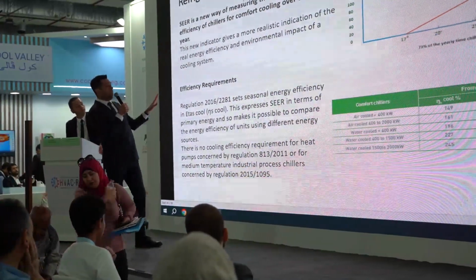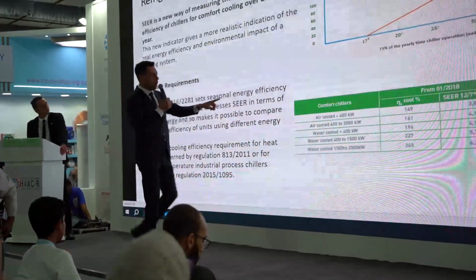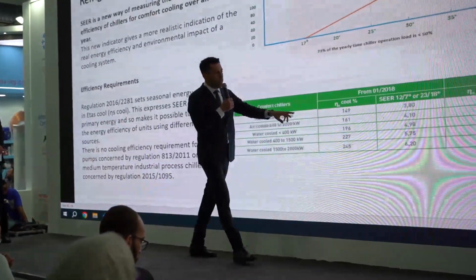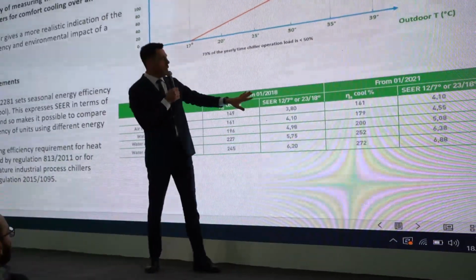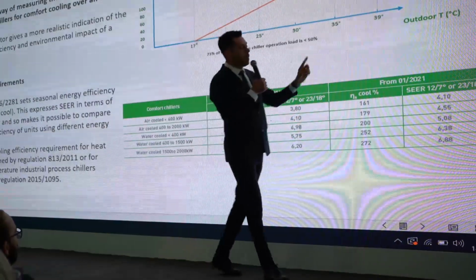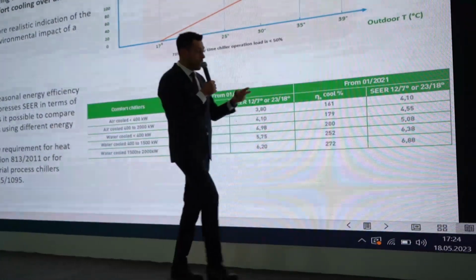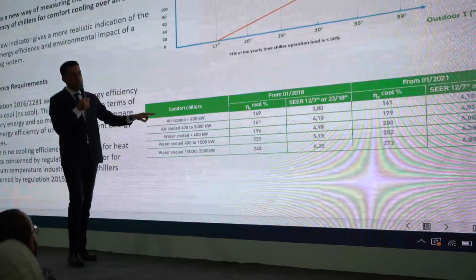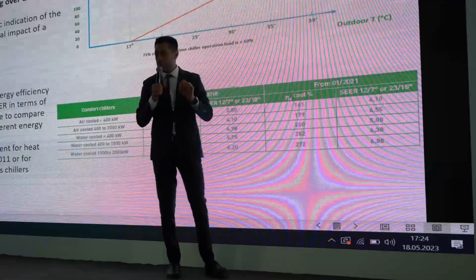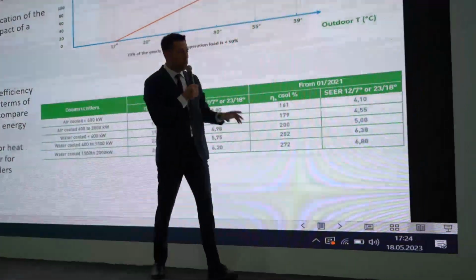Simply what they say for the comfort chillers, up to 400 kilowatt ETA value, seasonal energy efficiency, tier 1. But this has passed away. So now we are in tier number 2, the second stage, the next stage. They say less than 400 kilowatt of cooling, the ETA value has to be 161, and the minimum seasonal energy efficiency is going to be minimum 4.1.